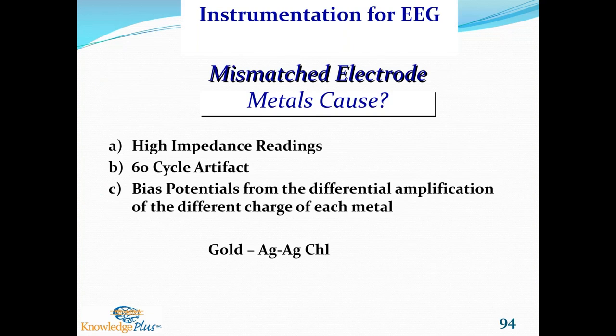If you had on a patient 1 gold electrode and 1 silver electrode, what would you see? And here we have gold and AG, AGCL. What would you see? Would you see high impedance readings, 60 cycle artifact, or bias potentials from the differential amplification of the different charge of the metal? And the answer is bias potentials, because each metal has a charge. When you have the difference between activity in 2 electrodes, it's going to amplify not only the brain activity, but also the difference in each electrode metal.